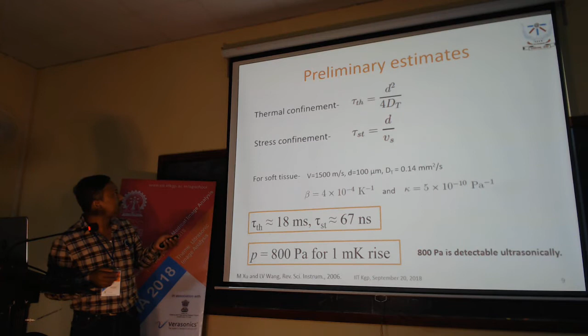So the thermal confinement time is given by d squared by 4D, where D is the thermal diffusivity of the tissue, and its value for a soft tissue is 0.14 millimeters squared per second, and stress confinement is defined by d by Vs, where Vs is the velocity of sound. If you put in all these values, you will have an estimate that the thermal confinement time is about 18 milliseconds, and the stress confinement time is 67 nanoseconds. That suggests what the pulse width of the laser should be. It should be less than 10 nanoseconds if we want to obtain a resolution of 100 micron.